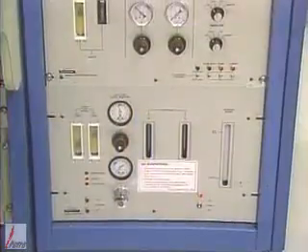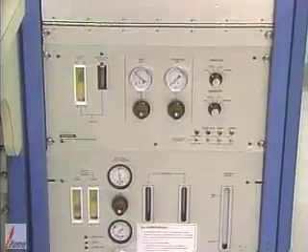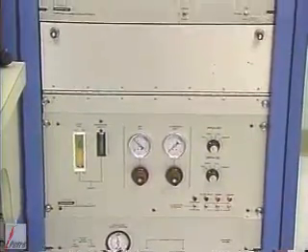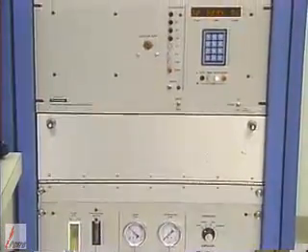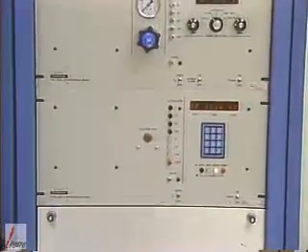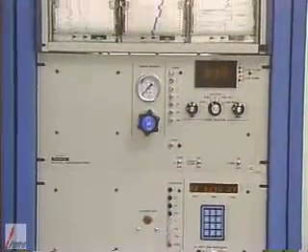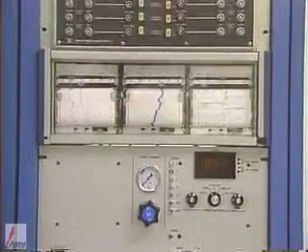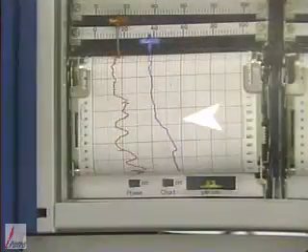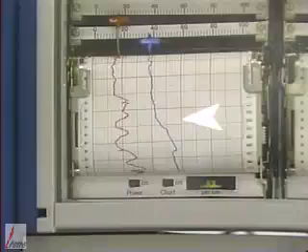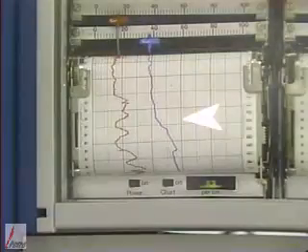A portion of the gas sample is split off to pass continuously through the total combustible gas detector, generally referred to as the hot wire detector. This detector produces a continuous reading, generally on a meter dial and a strip chart. This reading is a measure of all combustible gases in the sample.